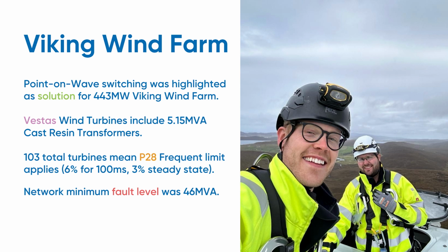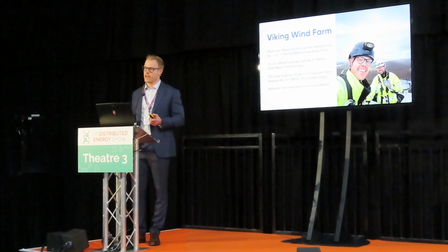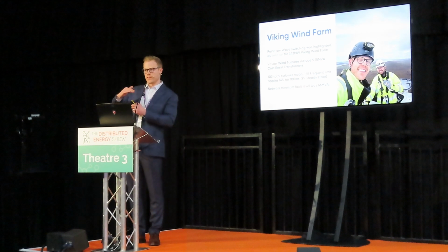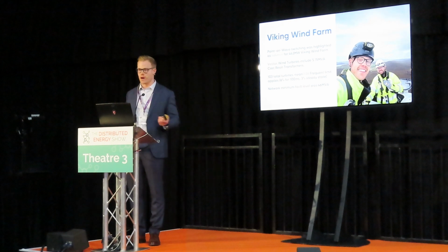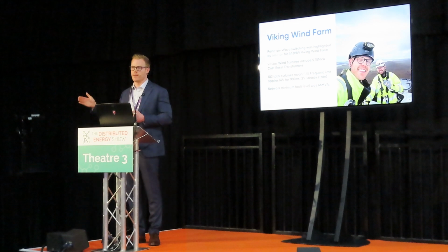For this reason, the Viking Wind Farm has an extra connection to the Shetland's 33 kV network. The idea being that if the HVDC goes down, they can energize the site from the 33 kV and keep the turbines powered and in preservation mode. Now, the problem is that the fault level on the Shetland Islands is 46 MVA, and we're trying to connect 103 5.15 MVA cast resin transformers. Because there's 103, the P28 standard means we have to apply the frequent limit, which is the tightest voltage depression limit, because we've got frequent operations. We're going to have 103 of these grid disturbances back to back.